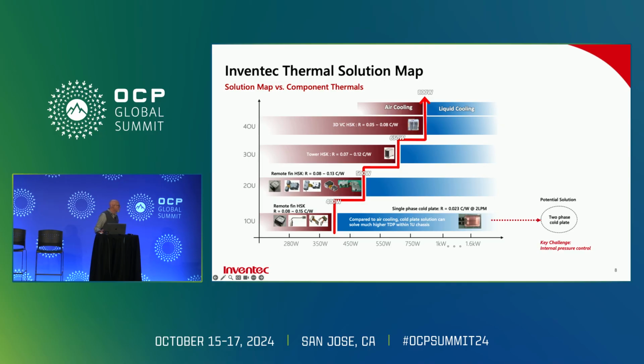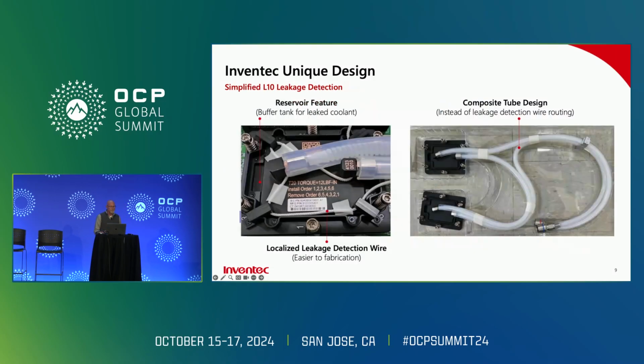And we have seen that the air-cooled versions, as the 1U shows, will top out at 400. But with the use of DLCs, we can get into the 1.4 kilowatt range with single phase. We are now working on the dual phase approach for liquid cooling, for direct liquid cooling, to help with these boxes.